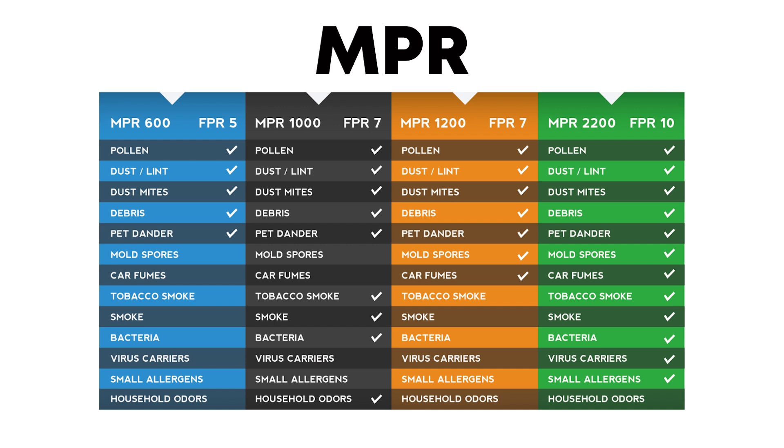MPR 1000 to 1200 can capture all of that as well as dander, smoke, and smog, and is similar to a MERV rating of 11 and FPR 7. MPR 1500 through 1900 have the ability to capture some of the trickiest particles, including those from bacteria and viruses, and is similar to a MERV rating of 13 and FPR 10.